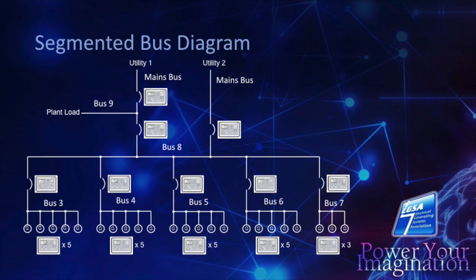So the system here is a one line of the segmented bus system, and it basically means that we can take any set of generators and provide power to any other side with tie breakers. In this case, it's pretty simple. We have the 5 groups of generators going to one bus, and then that bus can either provide through one breaker to export for the grid support, or through another breaker to provide power to the plant, or for a black start to the plant. We can open the utility breakers.